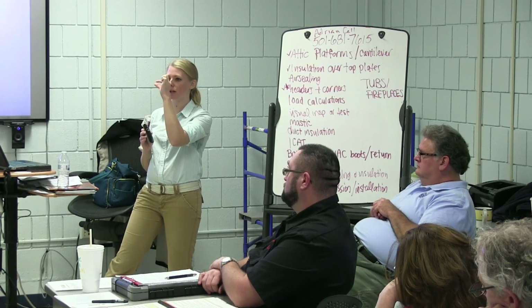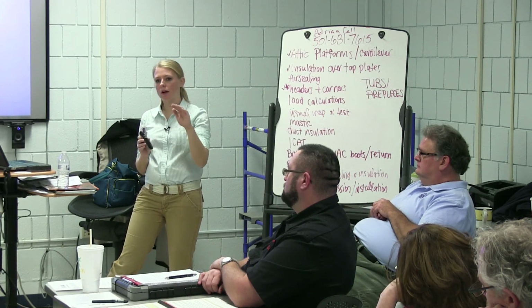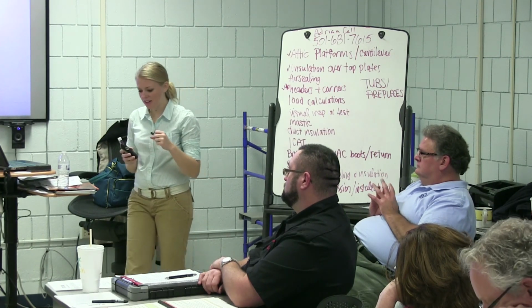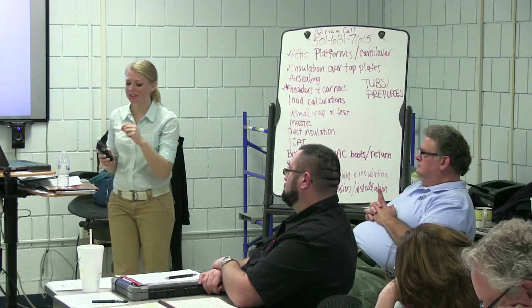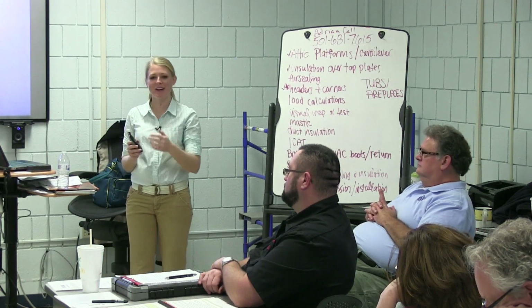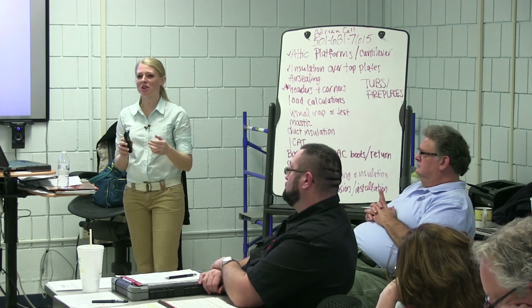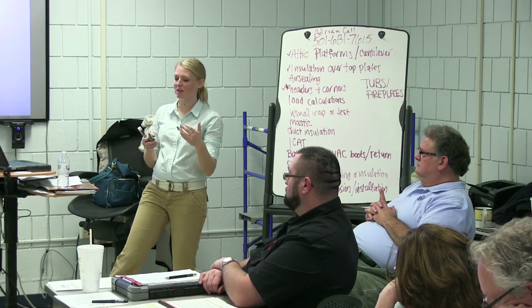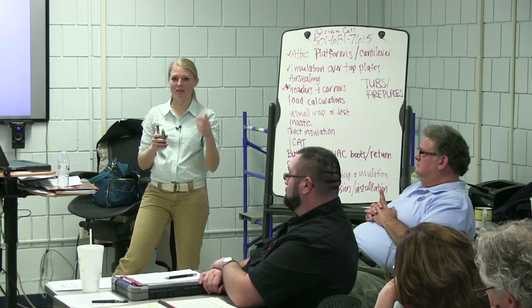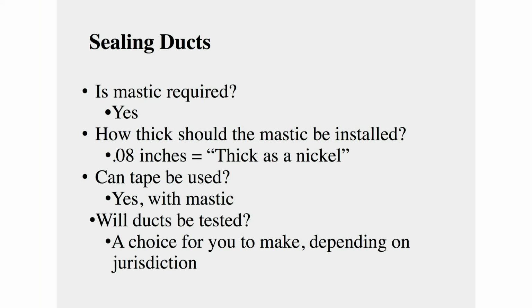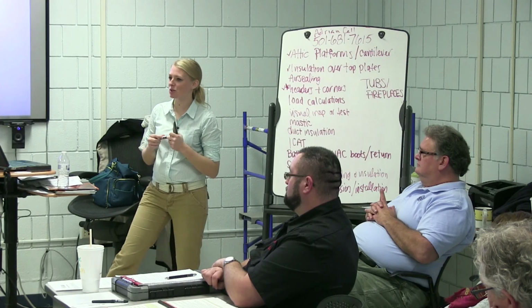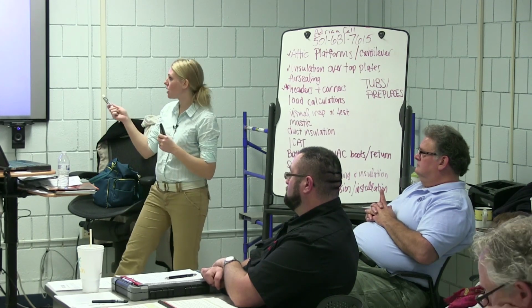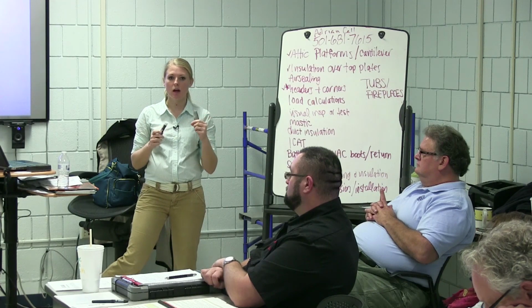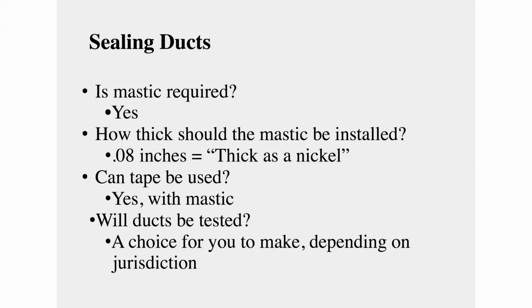So whenever you hold up a nickel, whatever that thickness is, make sure there's about that sort of layer across every joint and seam. I've seen guys go out there and paint them so nicely, and it's just barely coating it. And I'm like, y'all, as soon as we get any sort of change in temperature, especially when they're doing panned returns, this is all going to fall apart. This mastic is not enough. So, thick as a nickel. Can tape be used? Yes, tape can be used with mastic. So you can't just do tape anymore. You can use mastic tape as long as it is that 0.08 inches thick, and it meets 181. So it has 181 on it, which is the standard that this is referencing in here.